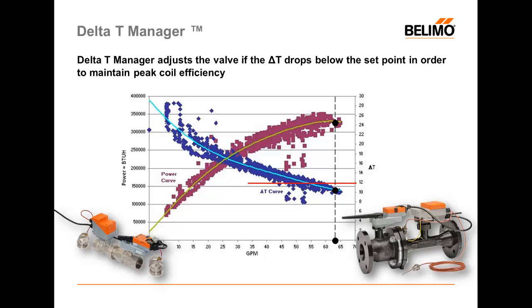With the Delta-T manager in place, we will restrict the flow through that valve. By restricting the flow, we'll drive the Delta-T back higher, but due to the inefficient nature of coils at high flow, we see little or no reduction to the amount of load that can be delivered to this space. So again, we're still achieving around 325,000 BTUs, but we're using significantly less water to do it.